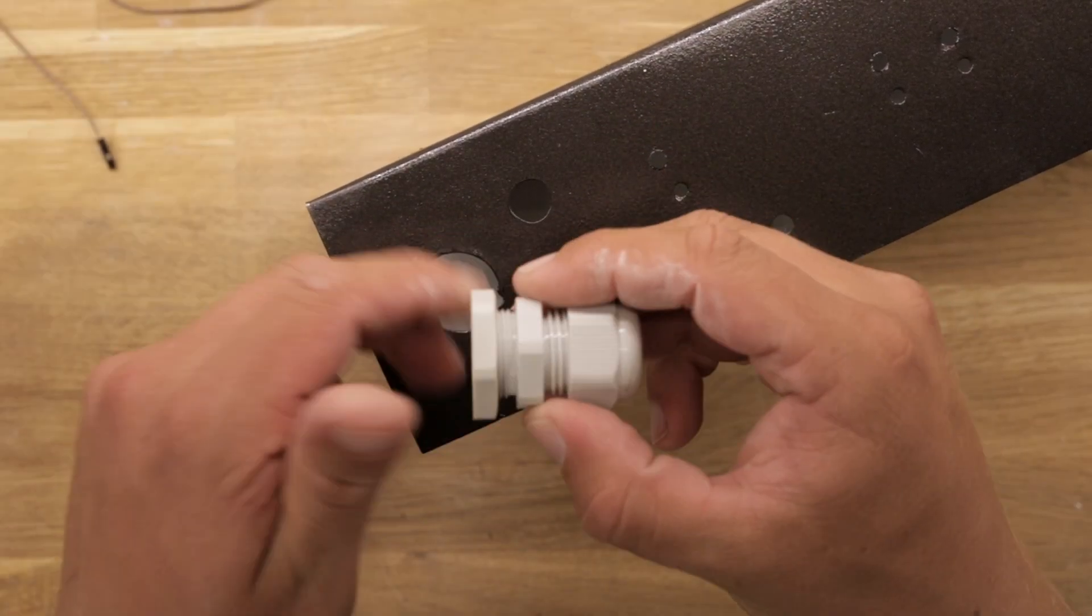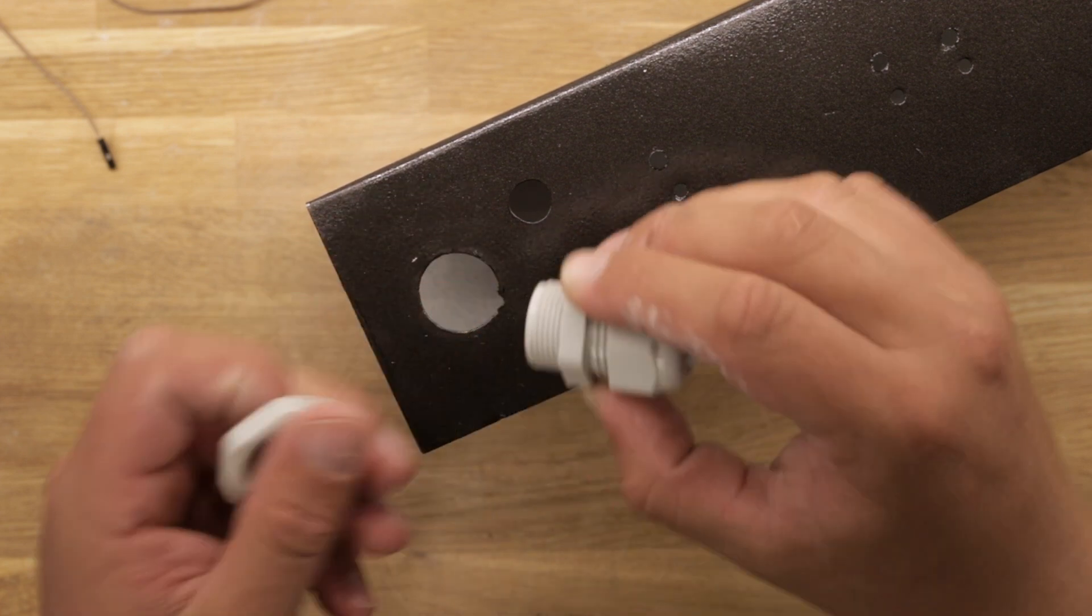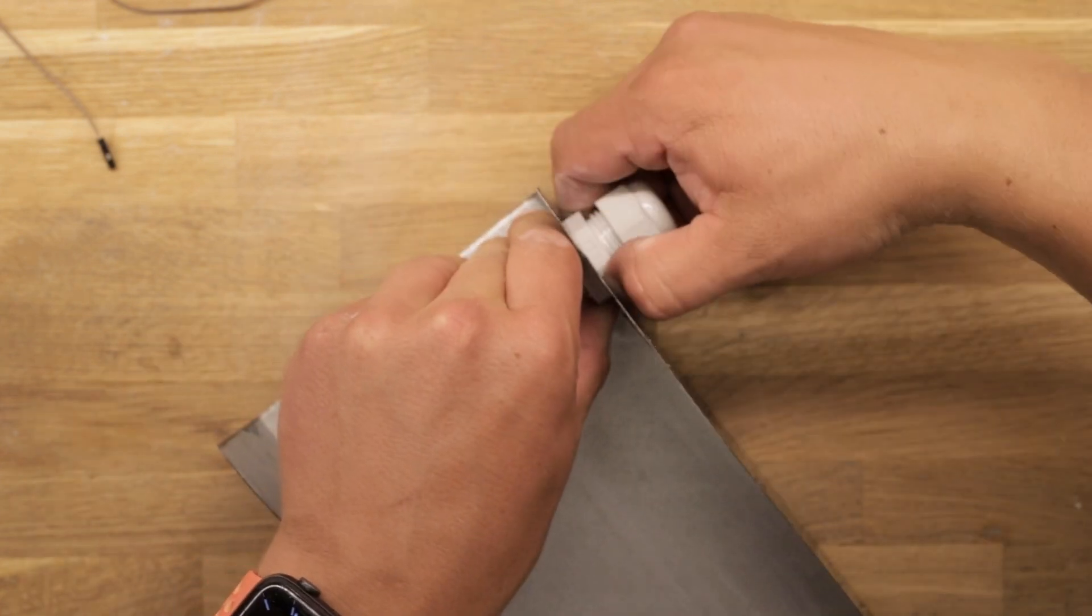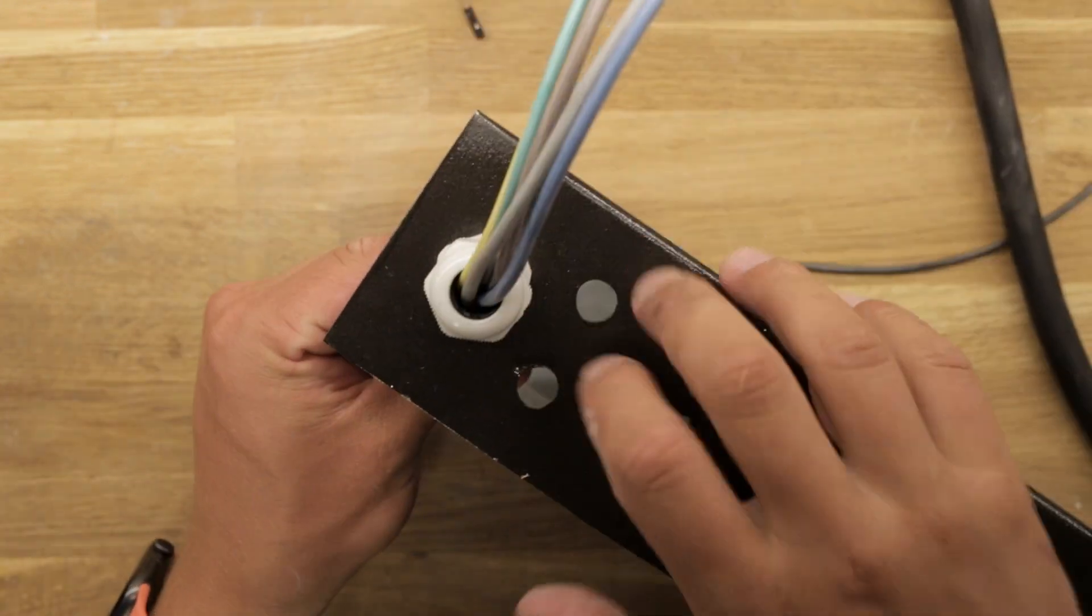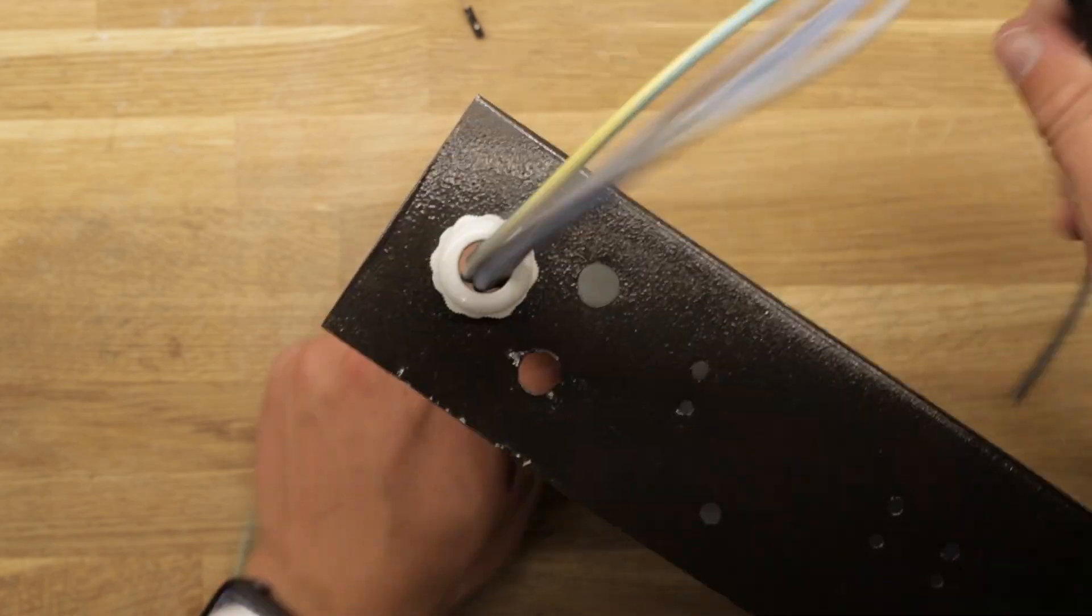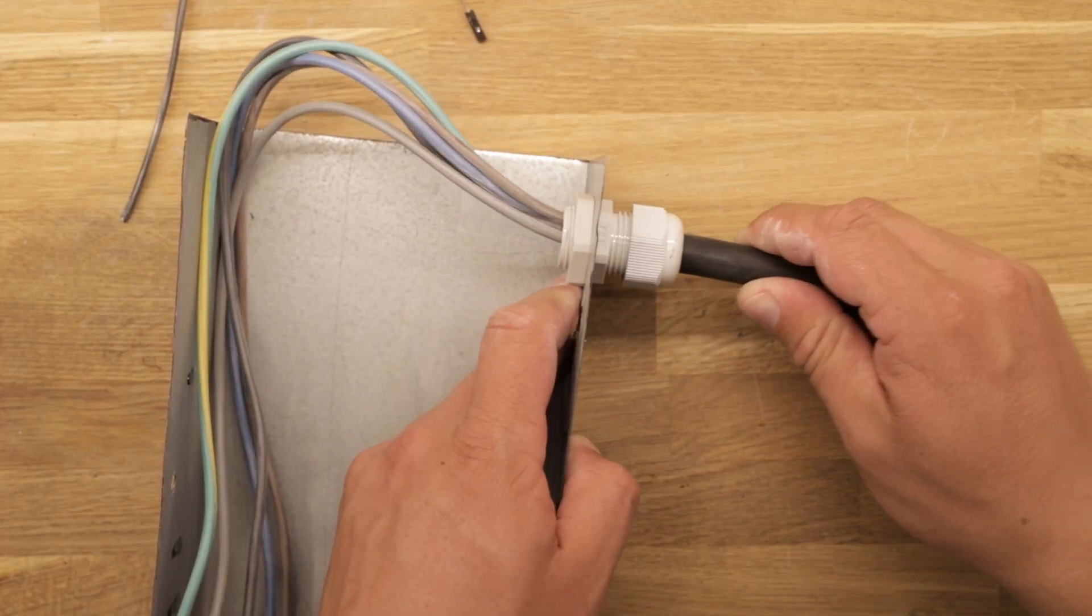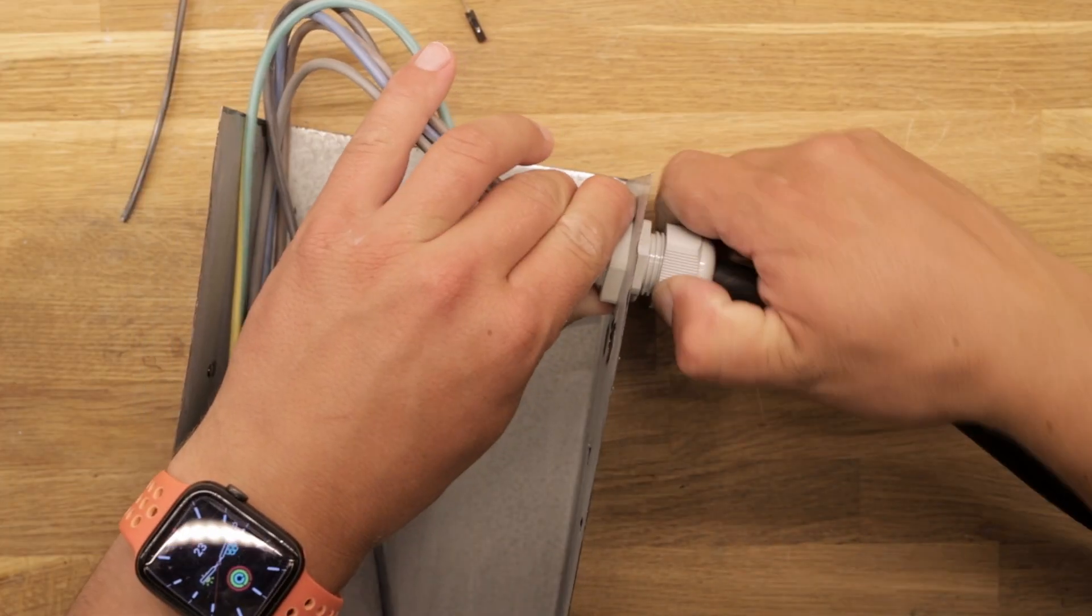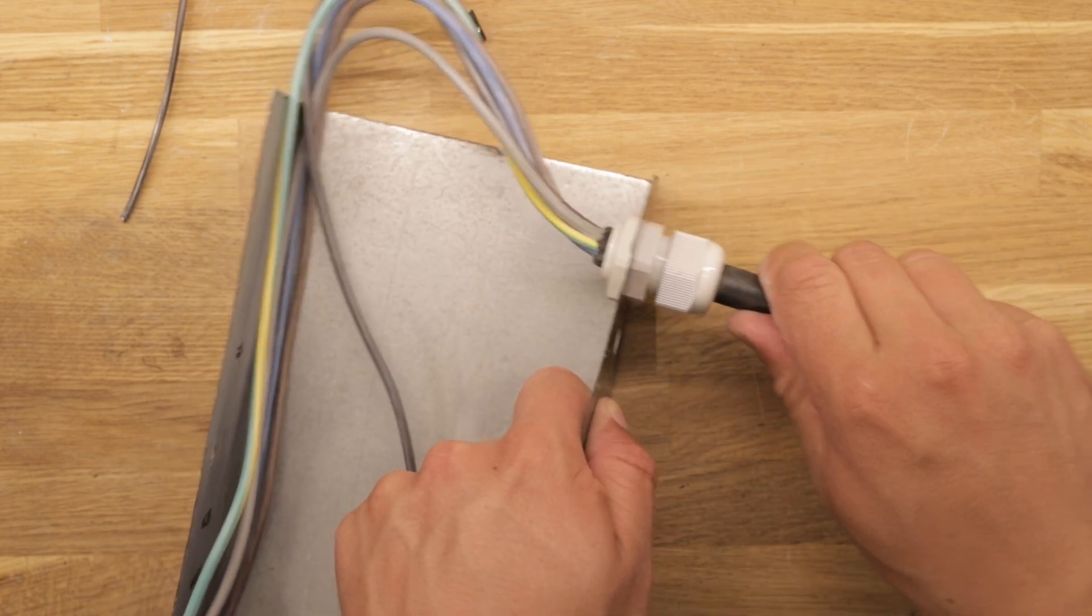Let's begin by mounting the PG cable gland for the power cable. The three-phase power cable has five conductors that are fed through the gland until it can tighten around the outer insulation. We give everything a little pull test to ensure that it is tightly secured.